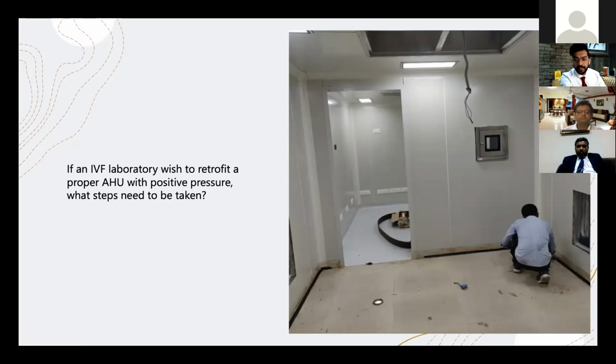Dr. Keshav adds a point: as correctly mentioned, AHUs are not always very expensive. It depends on capacity and what is installed. When handling two different rooms with different cleanliness requirements, you must design the AHU for the cleanest room, which needs the minimum level of particulates and gases. So over time, considering capital plus operating cost, you may end up using more expensive filters and replacing them often. Separation is generally a good idea, though it depends on the site, especially if the areas are too small.